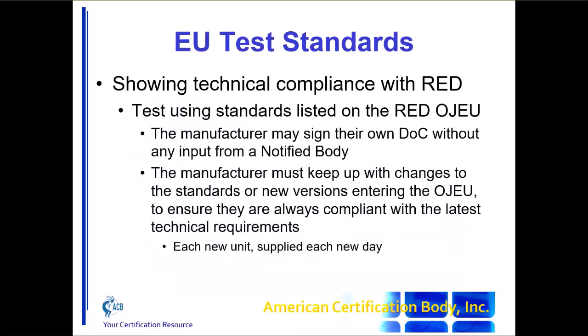If you've used test standards that are listed on the OJ, then the manufacturer can sign their own declaration of conformity without any input from a notified body. The manufacturer will need to keep up with any changes to the standards, as I mentioned before with my example of 3,000 products planned, but you've only sold 2,000 of them when the standard changes.